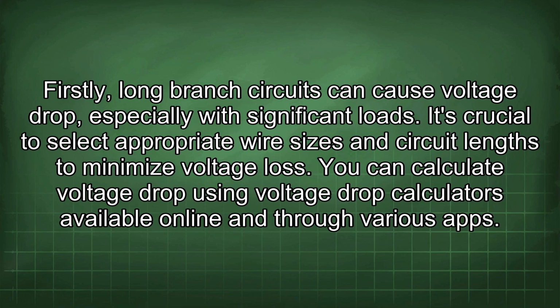Firstly, long branch circuits can cause voltage drop, especially with significant loads. It's crucial to select appropriate wire sizes and circuit lengths to minimize voltage loss. You can calculate voltage drop using voltage drop calculators available online and through various apps.